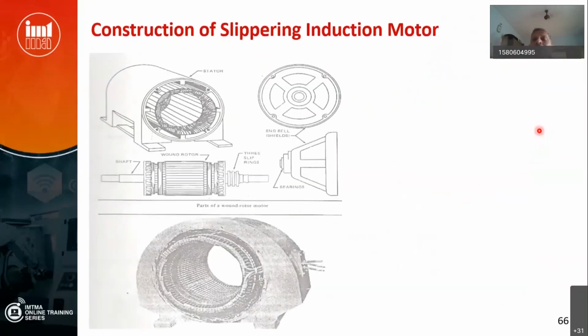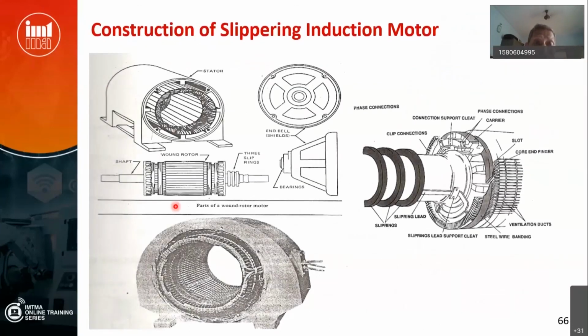In the slip ring induction motor, instead of bars, the rotor has a regular winding connected in star. Three free leads are connected to the slip rings, and these are taken outside through the brushes and terminated through resistors. The stator winding is the same, no change. These are all the slip rings, and this is the rotating portion. It has a regular winding: again a core of silicon steel stampings, with slots and wire winding, not bars like a squirrel cage. They are terminated at one end through these brushes, and outside we connect the resistance.